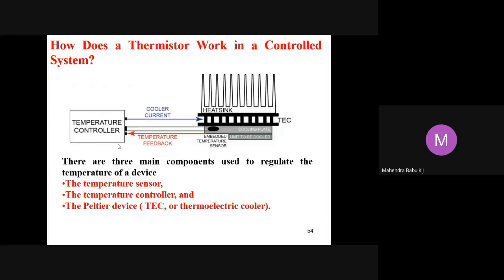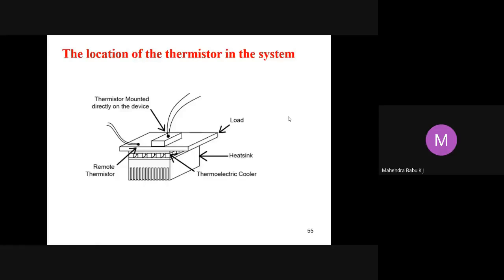The temperature controller is the main brain of the operation. It takes sensor information and compares it to what the unit to be cooled needs. That is the set point. Whatever the set point is, that is to be maintained. That can be done with the help of the temperature controller, which receives feedback from the sensor. Not only this, the location of the thermistor also plays a very important role. The location of a thermistor in a system affects both the stability as well as the accuracy of the control system. For best stability, the thermistor needs to be placed as close to the thermoelectric or resistive heater as possible. For best accuracy, the thermistor needs to be located close to the device requiring temperature control.